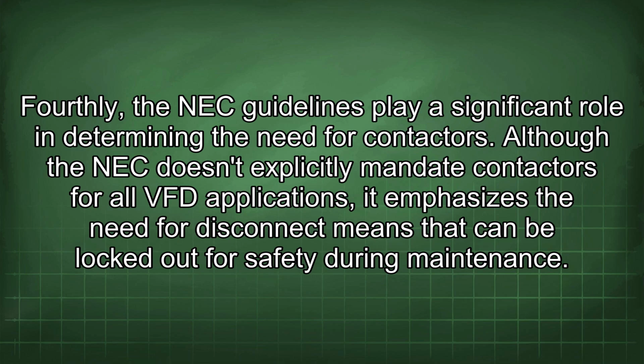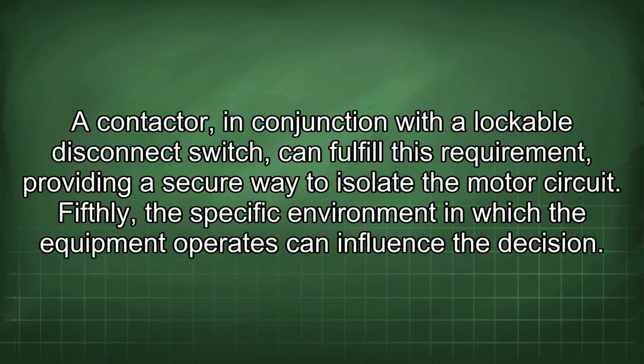Fourthly, the NEC guidelines play a significant role in determining the need for contactors. Although the NEC doesn't explicitly mandate contactors for all VFD applications, it emphasizes the need for disconnect means that can be locked out for safety during maintenance. A contactor, in conjunction with a lockable disconnect switch, can fulfill this requirement, providing a secure way to isolate the motor circuit.